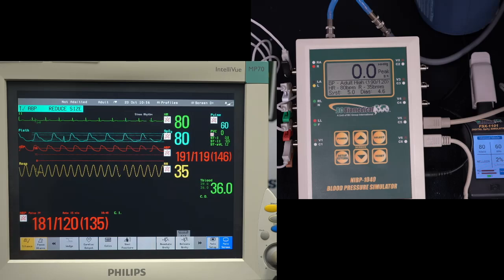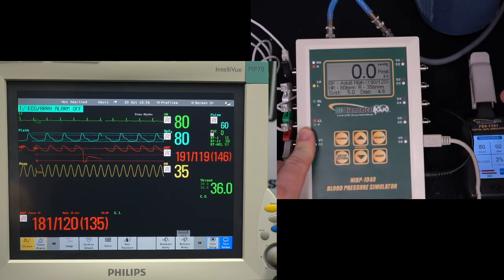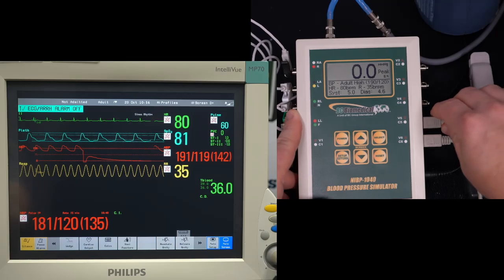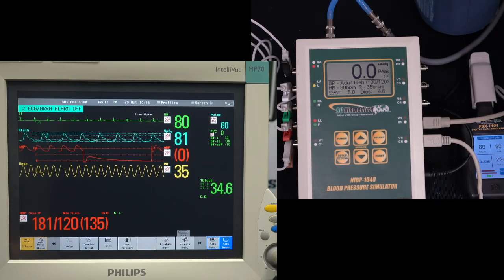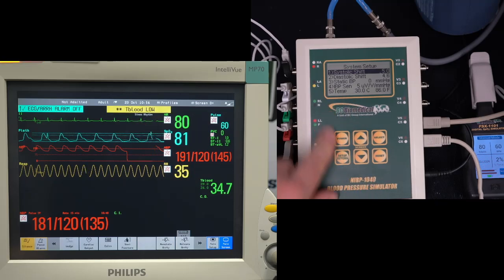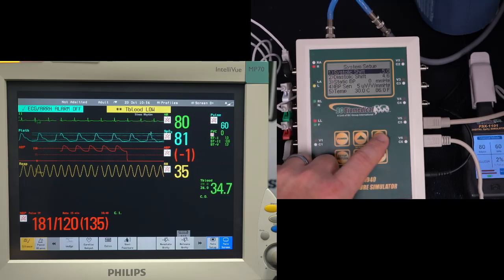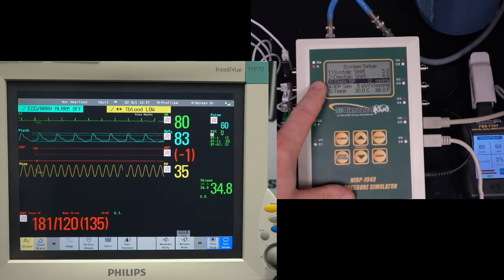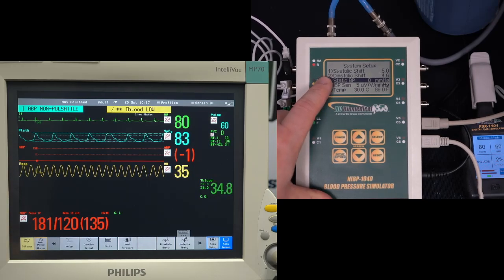Okay, so the other thing I want to demonstrate is how we can perform all this testing on our monitor. The other thing I didn't mention is that a lot of times when we connect the IBP cable, so I'm going to go ahead and reconnect this, the monitor detects that cable detachment, and so it requires you to do a 0 on the monitor. To do that, we go into the setup menu. This is also where we can select the shift for systolic and diastolic pressures. This is where we would go and do our 0 blood pressure. So I would go into the setup menu and have this set for 0.